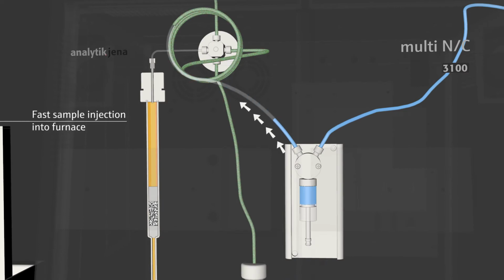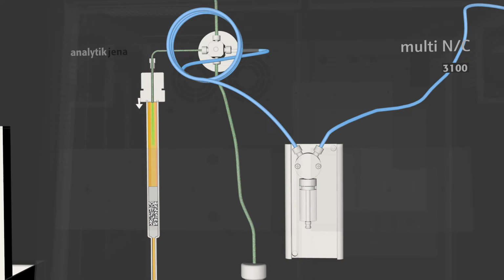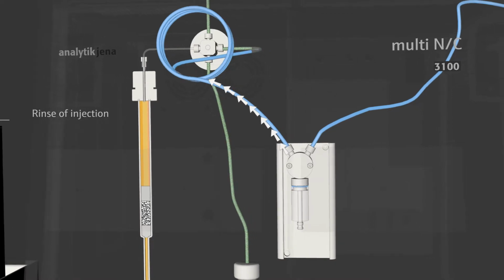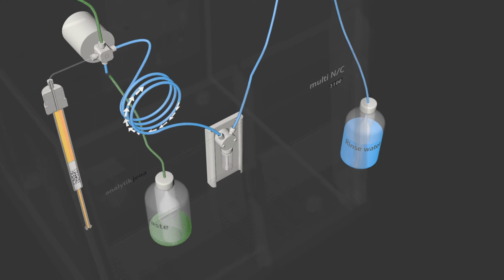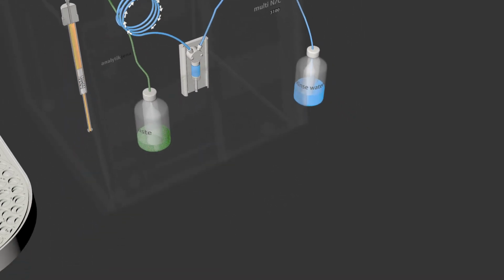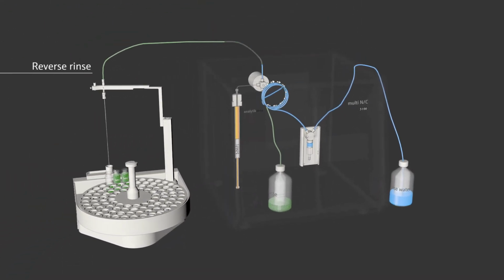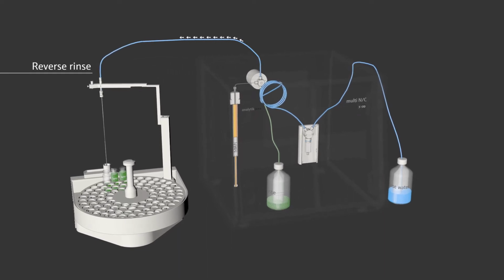A robust ceramic valve guarantees optimum particle handling. The sample is injected quickly, and all particles are completely transferred from the injection loop to the furnace. The injection needle and valve are effectively rinsed. This is followed by the reverse rinse of the sample aspiration tube and needle into the auto-sampler rinse station for full carryover control.